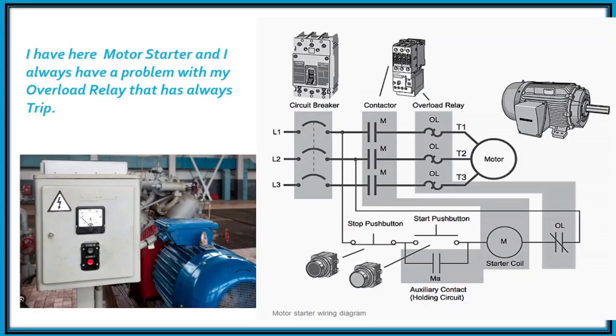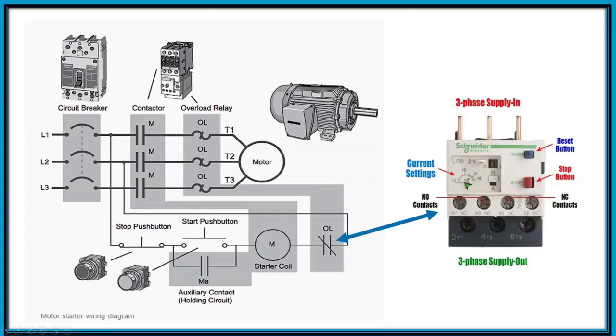I have here a motor starter that I always have a problem with, my overload relay that has always tripped. Do you know how to check an overload relay? This is the overload relay, and to check the overload relay using the multimeter, switch to ohms. The 95 and 96 should be closed, and the 97 and 98 should be open. If the 95 and 96 is open, even though you reset, that means we have a problem with the overload relay and it needs to be replaced.